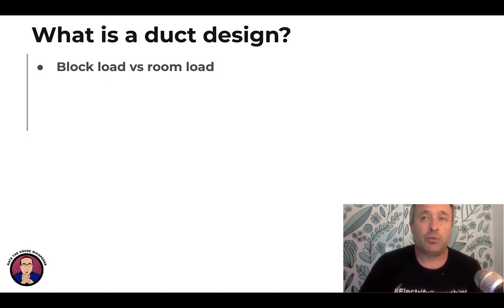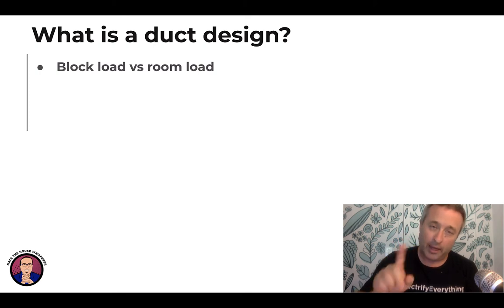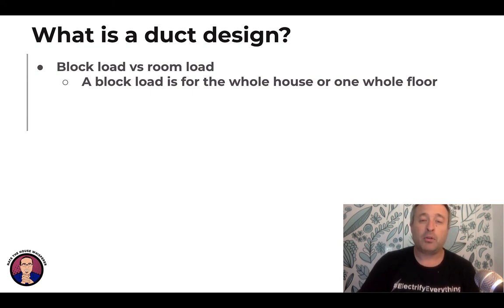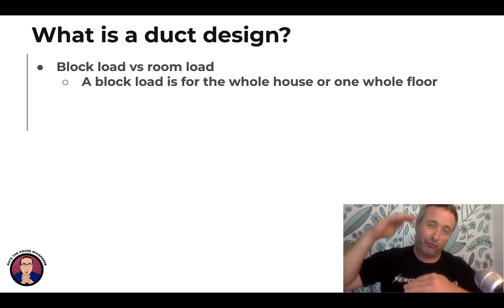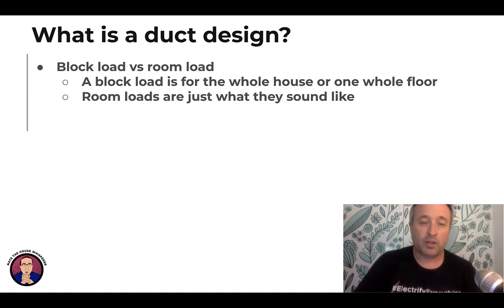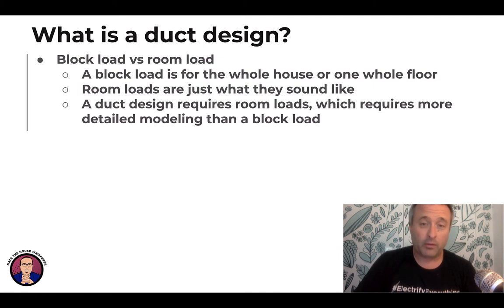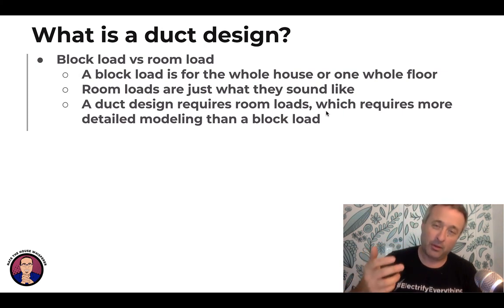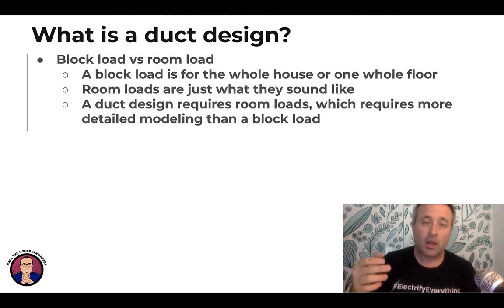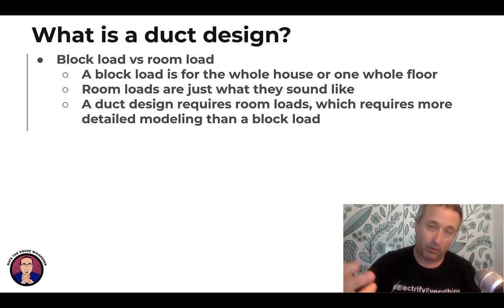When it comes to load calculations, there are two primary kinds: block load and room load. A duct design deals with the room load. A block load is for the entire house, or sometimes one floor — so a two-story house might have a first-floor load, second-floor load, and maybe a basement. Room loads are just what they sound like — how much do you need for each room. A duct design requires room loads, which requires a more detailed model than a block load. A block load I can run quickly with basic software in minutes, but a duct design typically takes hours — it's a whole other level of modeling, and it's going to cost extra.